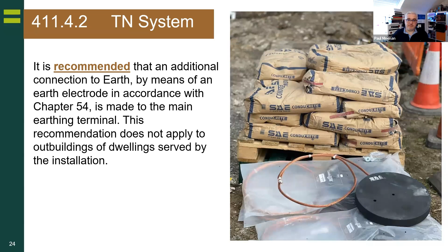There's been quite a lot of controversy around that, because that earth rod at your installation is generally only installed by the regional electricity company to mitigate supply cable faults. But when you start to look at where the industry is going, when you're switching out your network supply, you're going to need a local earth electrode. So you can see where this has come from. Right, one of the more controversial items that arrived in the 18th edition, 421.1.7, and by the way, it is for earth bonding at the moment, but when you switch the installation out, it will do both.